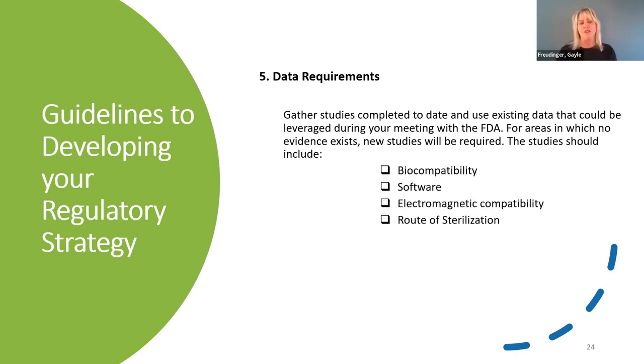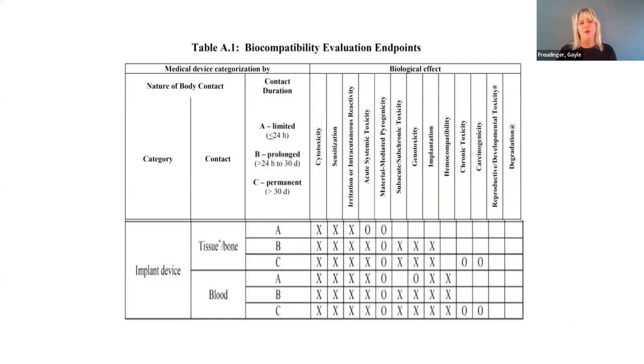Okay, so there are the data requirements. And here's an example of biocompatibility evaluation endpoints. Maybe Shana, quickly, you could highlight how this is used. Sure. One thing you have to be very aware of when you are looking at the safety of a device in terms of biocompatibility is the contact duration. If it's just in the body for 24 hours, the testing is going to be a lot less than if it's a permanent device that's defined as being implanted for greater than 30 days.